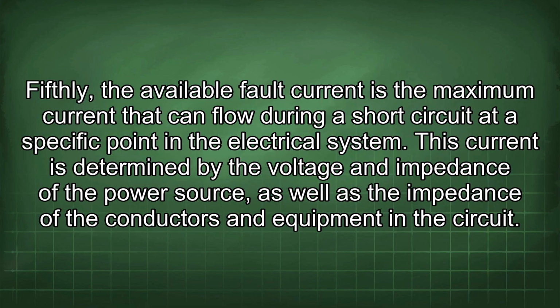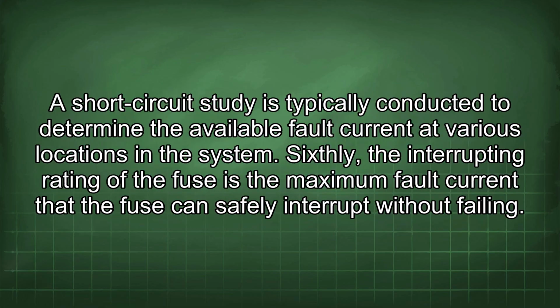Fifthly, the available fault current is the maximum current that can flow during a short circuit at a specific point in the electrical system. This current is determined by the voltage and impedance of the power source, as well as the impedance of the conductors and equipment in the circuit. A short circuit study is typically conducted to determine the available fault current at various locations in the system.